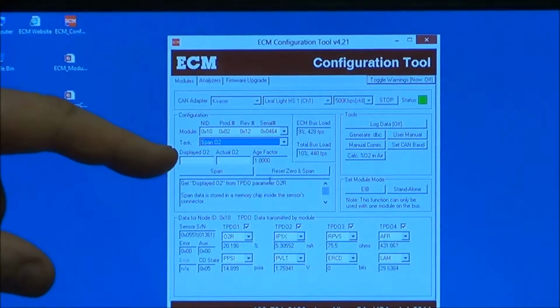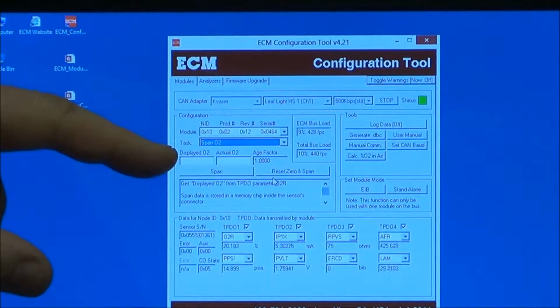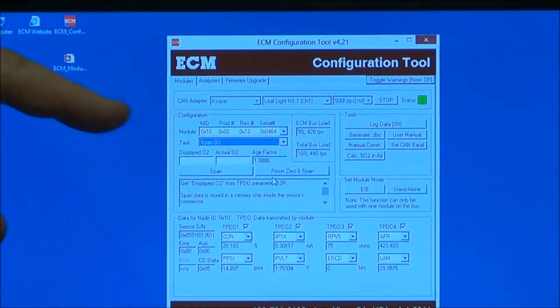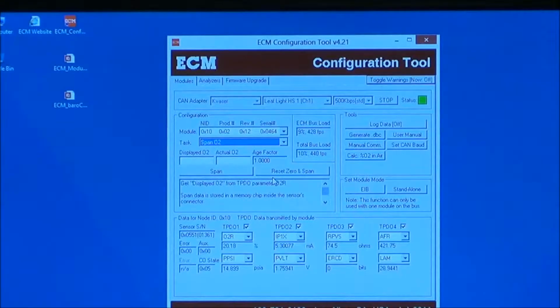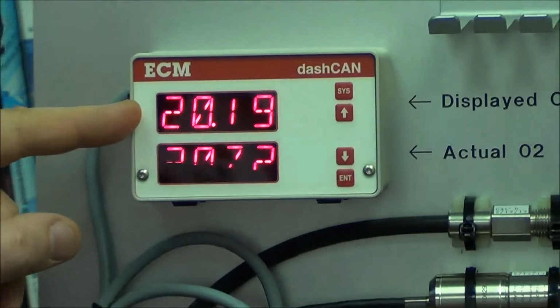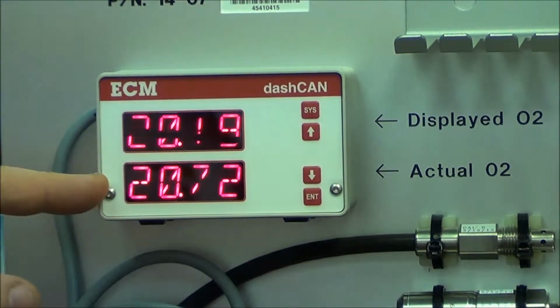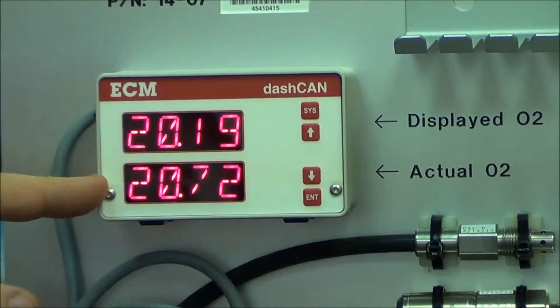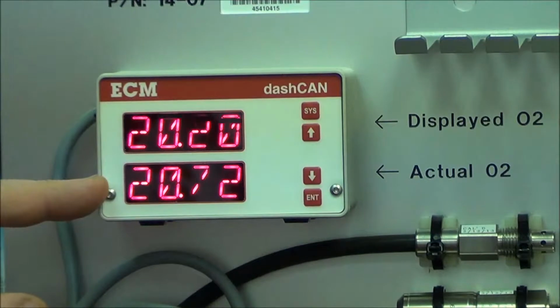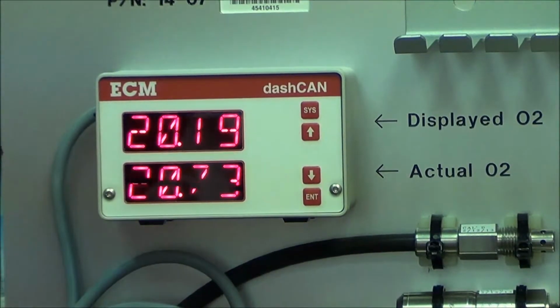You're going to open up two windows. One says displayed O2, the other one says actual O2. The displayed O2 is on the upper part of the display. It's the O2 displayed by the Lambda CAN with that sensor attached. The actual O2 is the right answer.